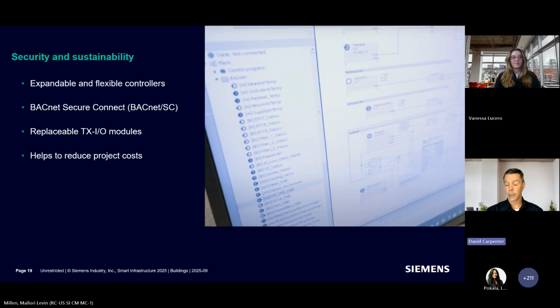Also, the I/O modules are able to be replaced in a hot swap. The module itself can be pulled out, leaving the I/O and all of the wiring in place, and put back in without ever having to take the system offline. Meaning that having just a handful of I/O modules on the site gives instant replacement and instant redundancy if the need arose, which ultimately reduces project costs. It keeps spare parts on hand to a minimum while providing a very high level of redundancy and security for the customer.